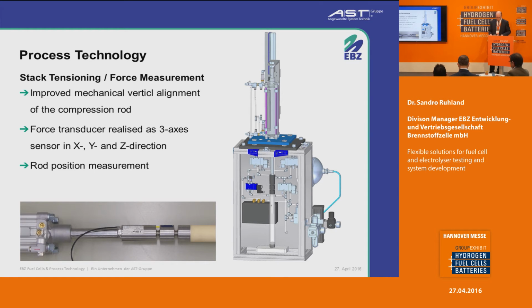The second thing is we integrated a force transducer which can measure in 3 axes. The advantage is that we can directly see in which direction the force goes into the stack. The last thing about this subsystem is a rod position measurement that can also help to see, during heat up or cooling down of the stack inside the furnace, how or in which way the height of the stack is changing during the thermal cycle.